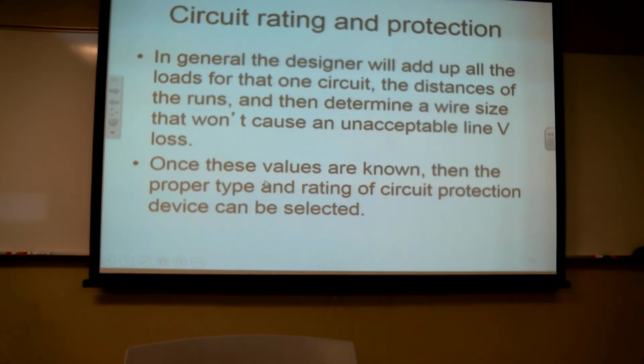So let's say I have a total of 5 amp users. I'm going to build it to where it can handle 10 amps. And then I'm going to shoot for the middle. I'll say, let's use an 8 amp circuit breaker. That way, the circuit protection will pop out at 8 amps, which is above what the total load's going to be, but below what the melting point of the wire is going to be, right?